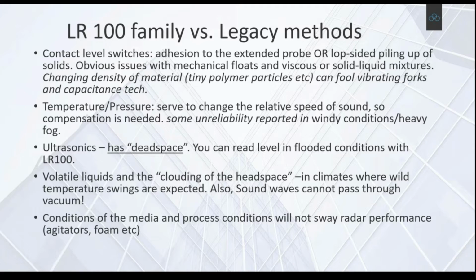When I mentioned dead space earlier, if the level of the liquid is too close to the face of the ultrasonic transducer, it will not read reliably, or it will fail high, or give you an error message because it cannot process it - the time from emission of the ultrasonic pulse to the surface and back is too short to give a meaningful reading. It's such a short time interval, but that's not an issue with radar.